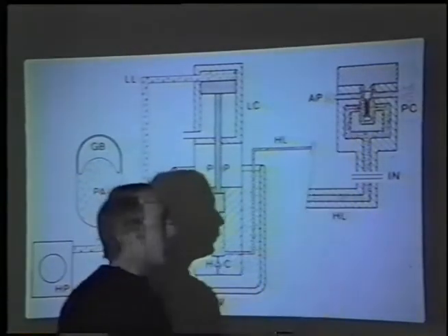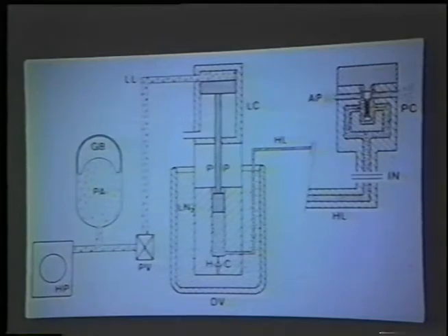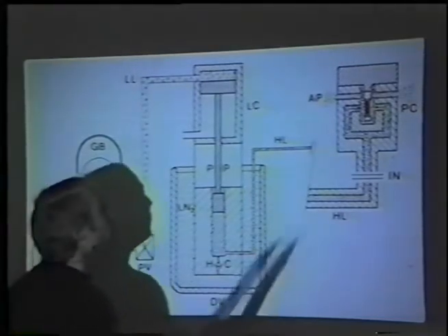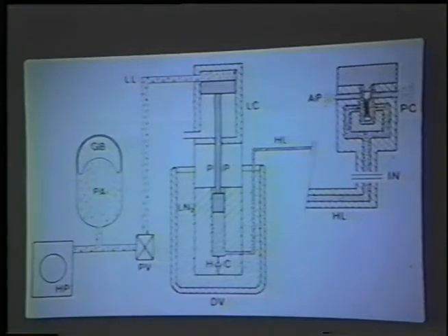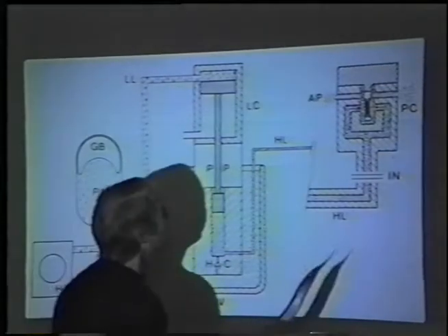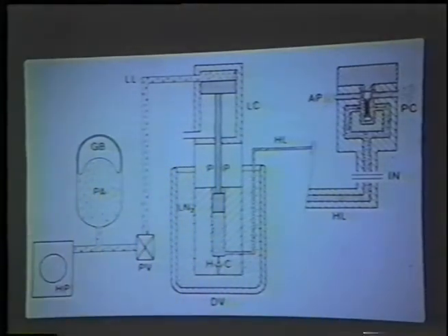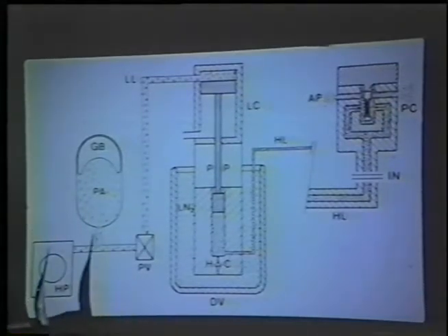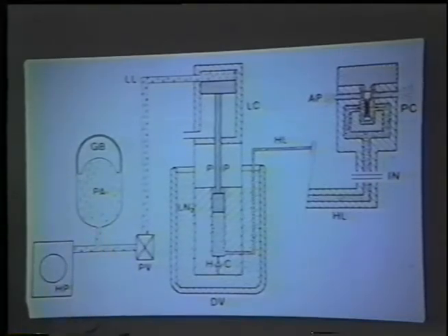The forces on the sample carrier and on the sample holder itself, as you might imagine, are tremendous. We had to modify them to get them to work at all. That's why ours is the only working machine. As they were originally supplied, the sample carriers were standard gold alloy carriers, one of which had a hemispherical depression, the other one had a cylindrical depression. That meant that during freezing, the sample carriers could move relative to one another and could move apart.